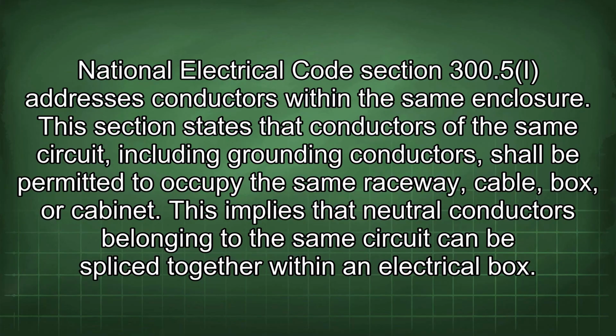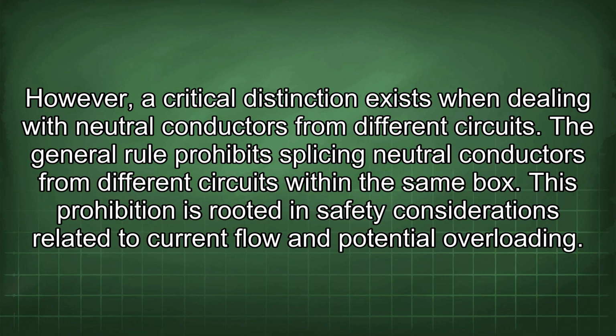National Electrical Code Section 300.5 addresses conductors within the same enclosure. This section states that conductors of the same circuit, including grounding conductors, shall be permitted to occupy the same raceway, cable, box, or cabinet. This implies that neutral conductors belonging to the same circuit can be spliced together within an electrical box. However, a critical distinction exists when dealing with neutral conductors from different circuits.